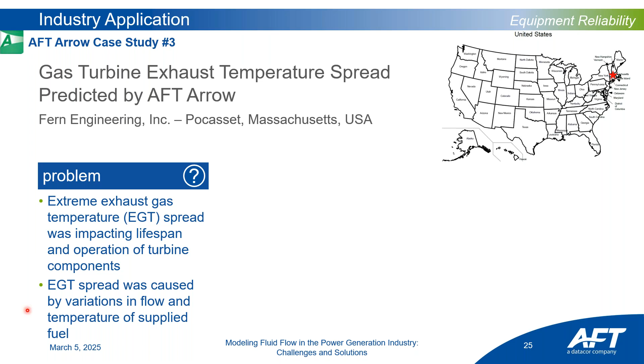Their problem is an issue that happens with fuel supply to turbines called exhaust gas temperature spread, or EGT spread. If you don't have even distribution of flow and temperature, it can impact the reliability and lifespan of operation of the gas turbine, basically caused by uneven distributions of flow and temperature.